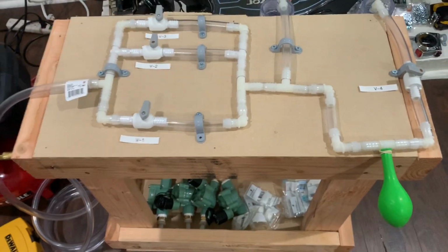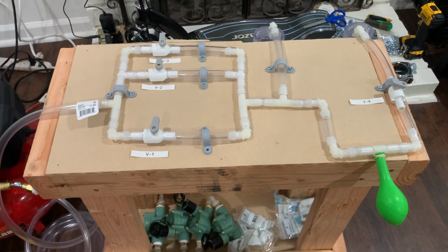We'll focus right here. And you can see that as I begin to open up the valve, we are bubbling through, and that was the effective expiration. So you can see now the balloon is slightly less inflated. Now it's sitting at whatever that peak pressure is, so around 5 or so centimeters of H2O. And we have maintained that pressure in the lungs. I've now shut off all of the valves. And that is the simple example of how this mechanical ventilator works.